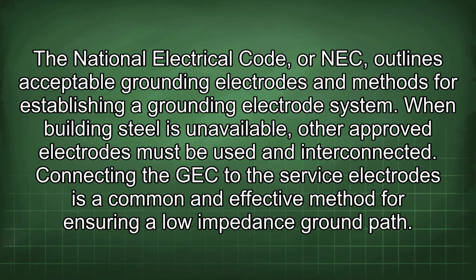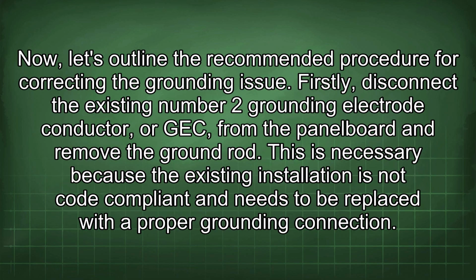The National Electrical Code, or NEC, outlines acceptable grounding electrodes and methods for establishing a grounding electrode system. When building steel is unavailable, other approved electrodes must be used and interconnected. Connecting the GEC to the service electrodes is a common and effective method for ensuring a low impedance ground path. Now, let's outline the recommended procedure for correcting the grounding issue.